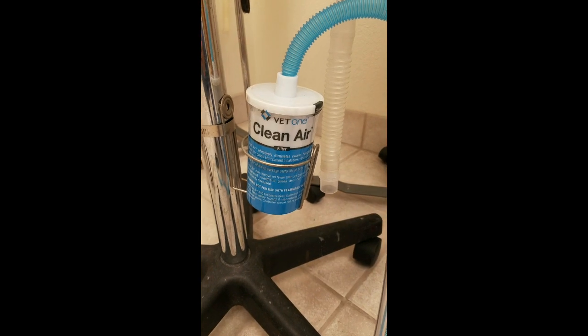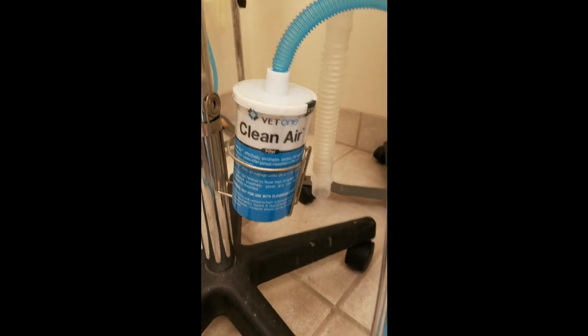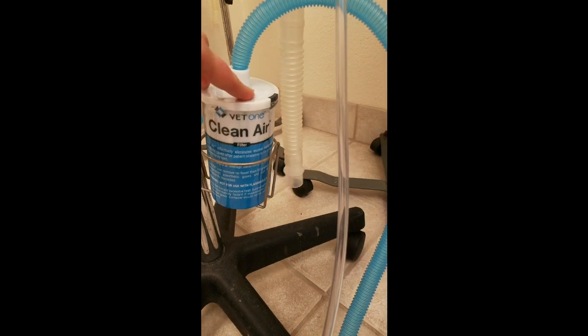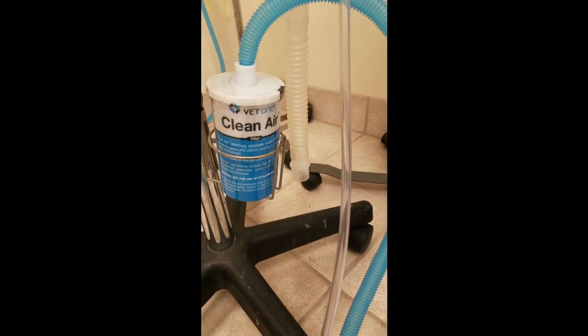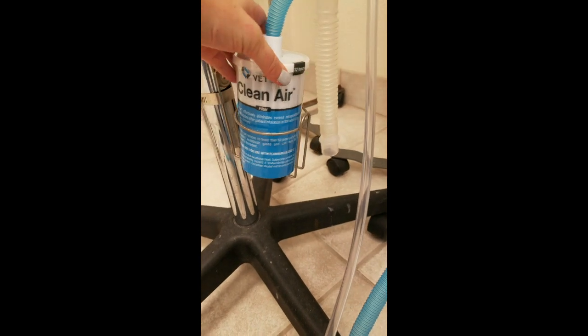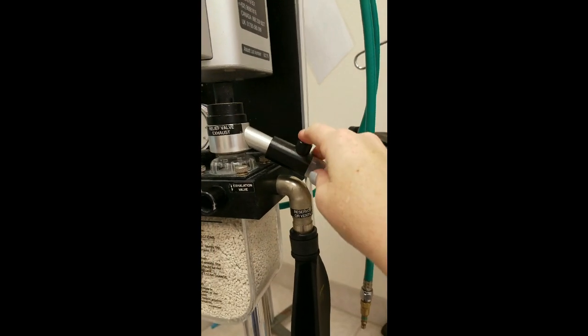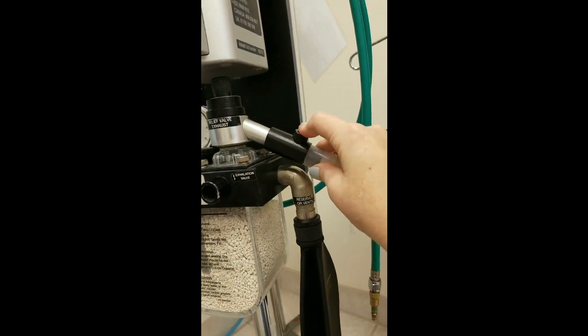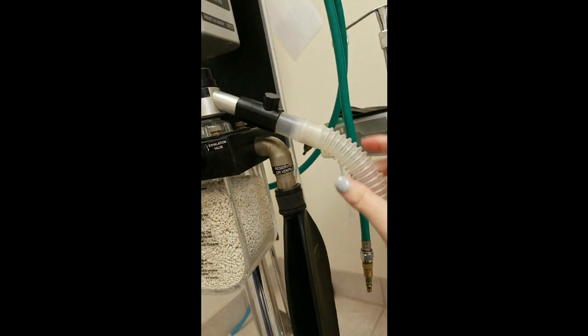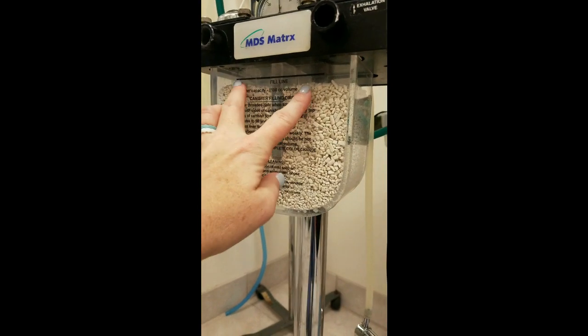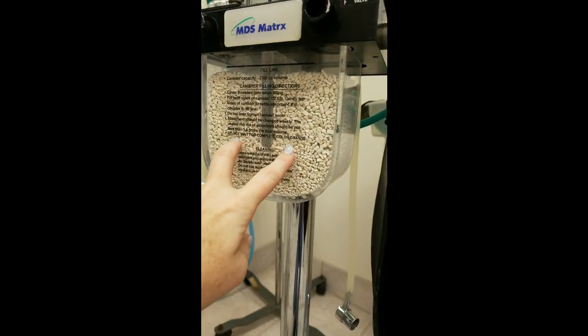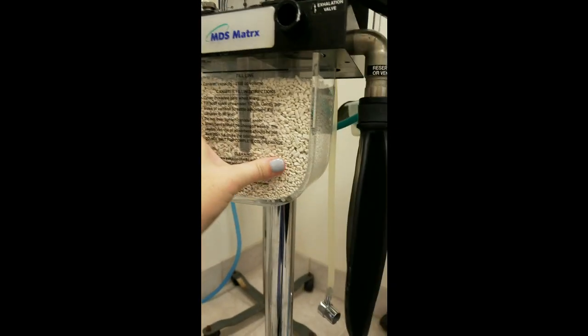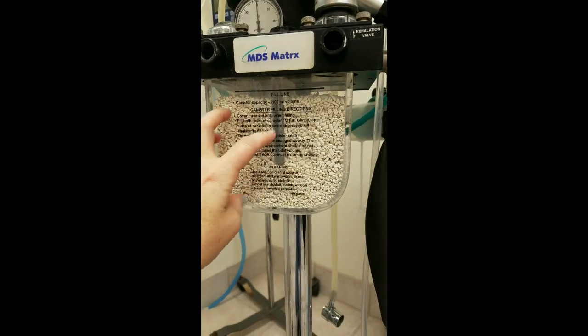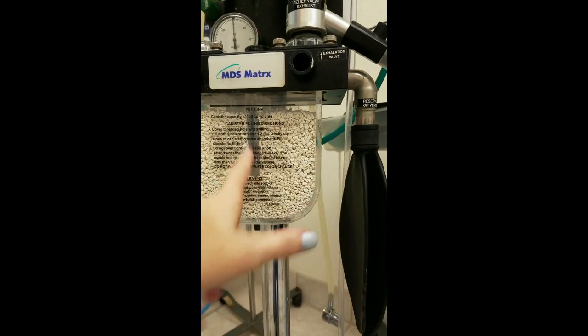This is the scavenger container, and this is where all the excess gas goes after the patient inhales and exhales. And this is our pop-off valve. This allows excess gas to exit the anesthetic circuit and then enter into the scavenger. This is the soda lime. This will turn purple when it's ready to change. And then also this contains the carbon dioxide and water vapor that comes out of the patient.